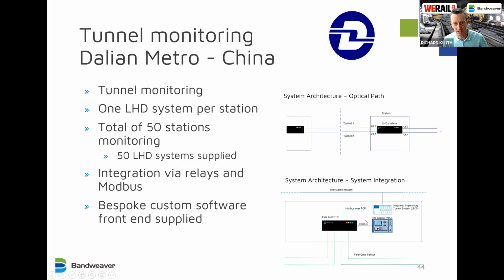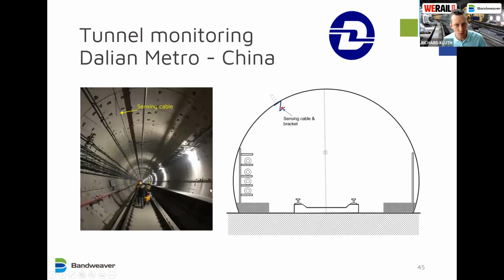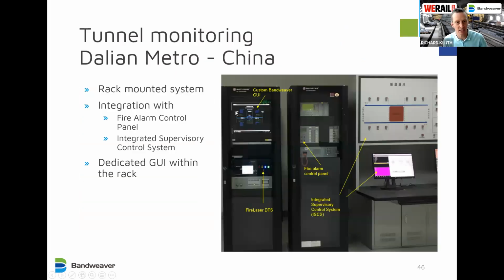Integration was via relays and Modbus, and there's also some bespoke custom software I'll show you in one of the slides. The cable was installed at a ceiling just offset to the left. You can see it there in the photo and the schematic. And it was a rack mounted system. Here we can see within the control room. So this is the fire laser linear heat detection system here. It's connected to the fire control panel in the rack next to it. Also, the integrated supervisory control system, the ISCS, is in the same room via Modbus.